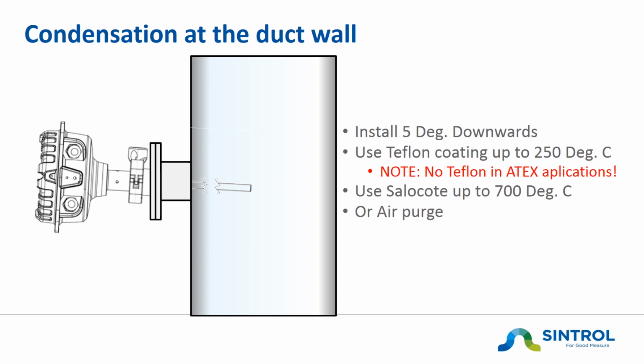Another possibility to avoid bridging and bad influences to the measurement is to use an air purge. That can be installed here in between the flange and the instrument. It will dry out the gas and keep the measurement clean.